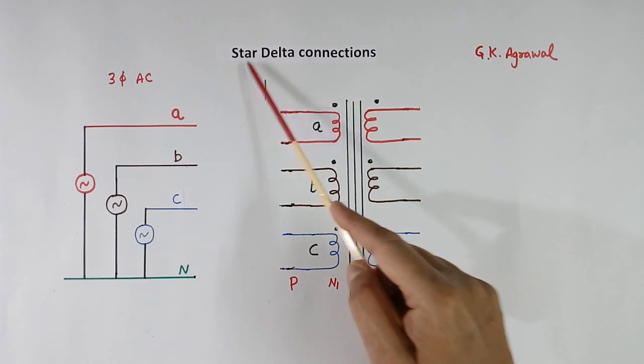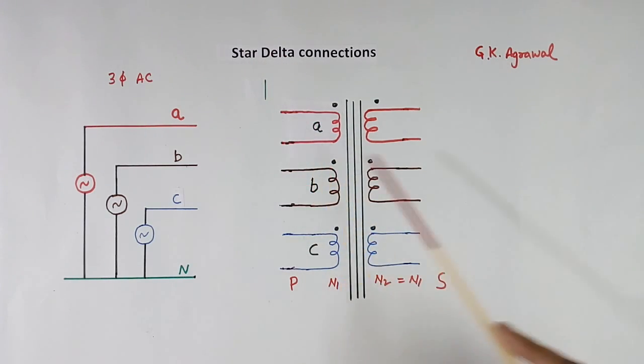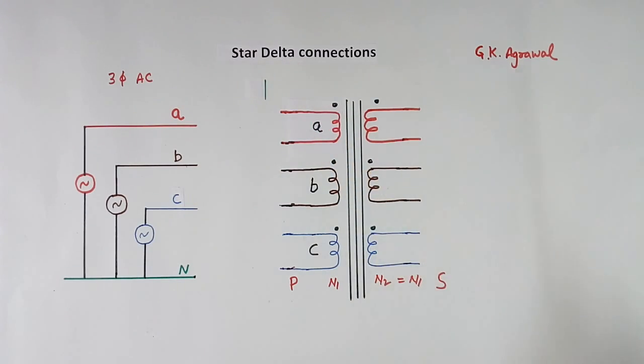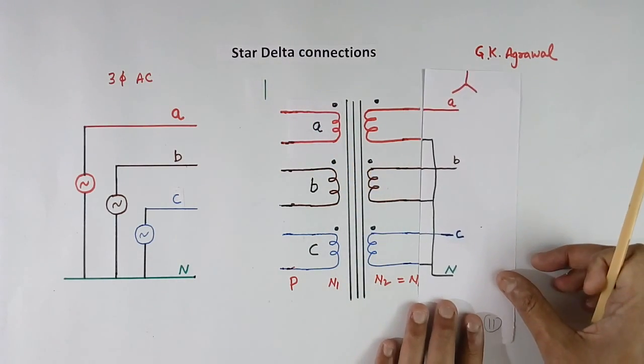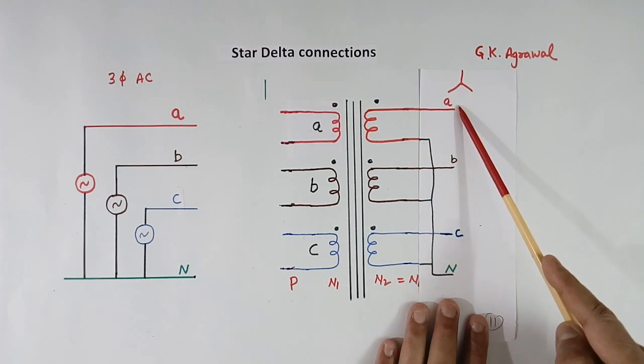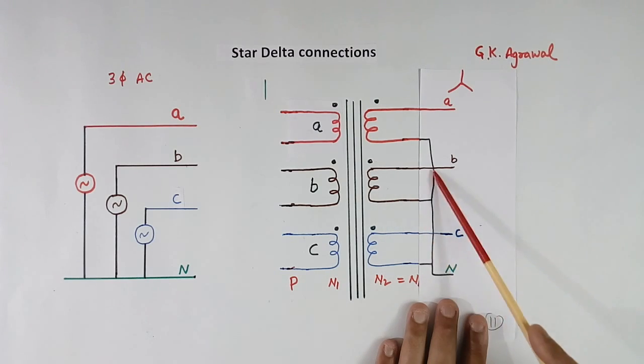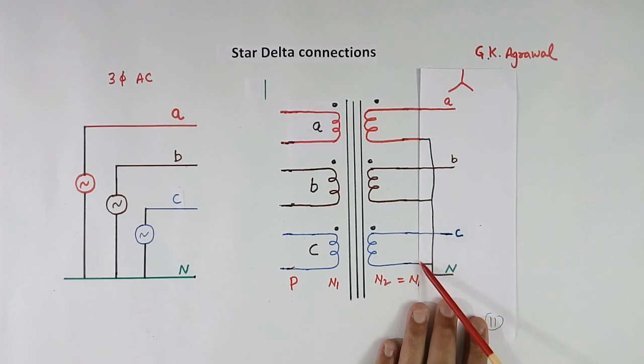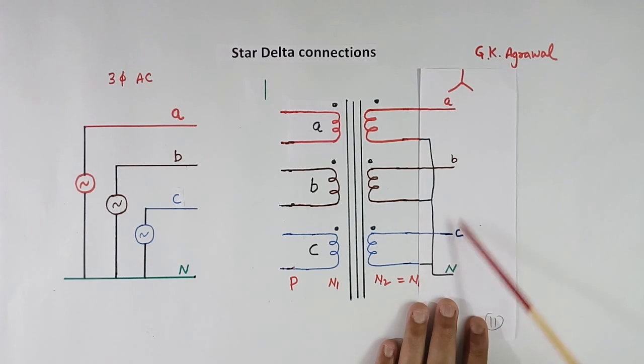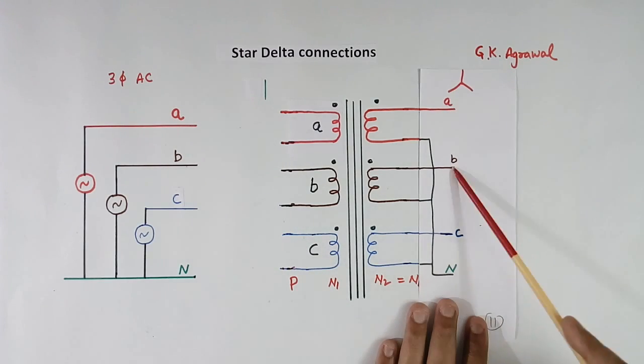We learned star and delta connection of the primary. Now the secondary can also be connected in star and delta both ways. In star connection, one terminal of each phase — A, B, C — goes to the load. The other terminals of all 3 windings are shorted together and called neutral. So we get 4 wires. The voltage of each phase winding appears between that line and neutral.